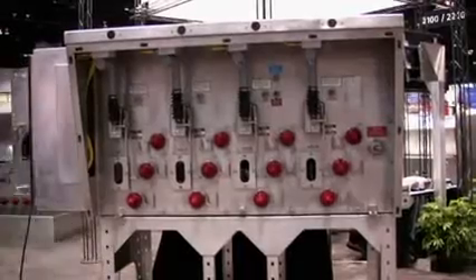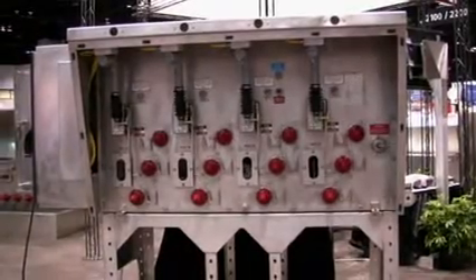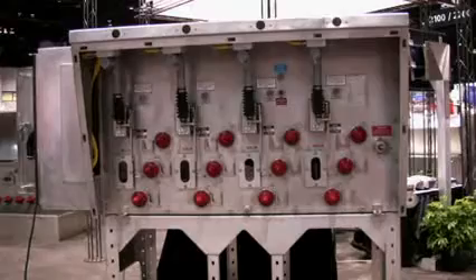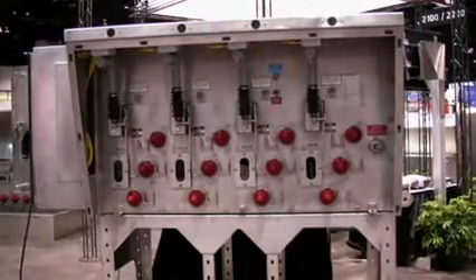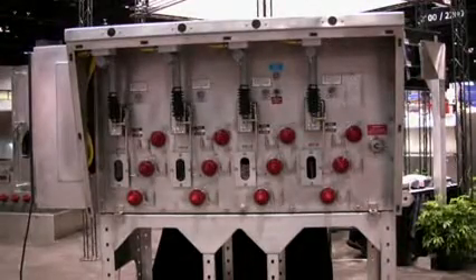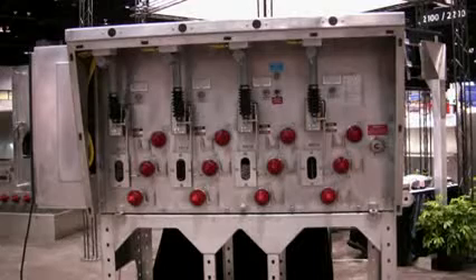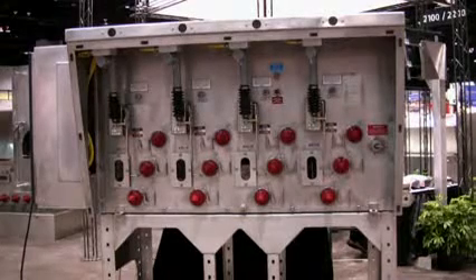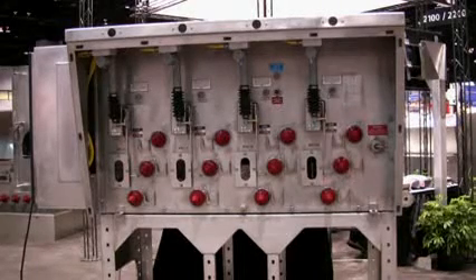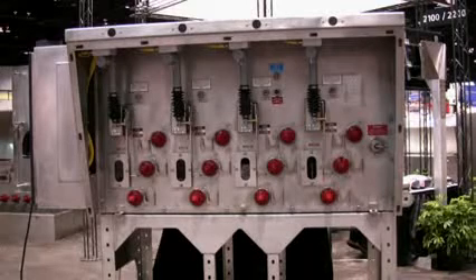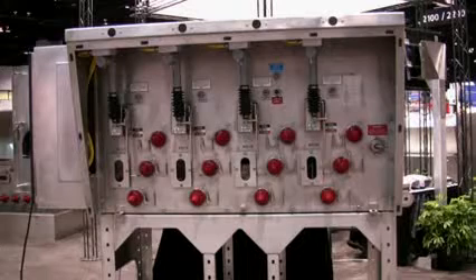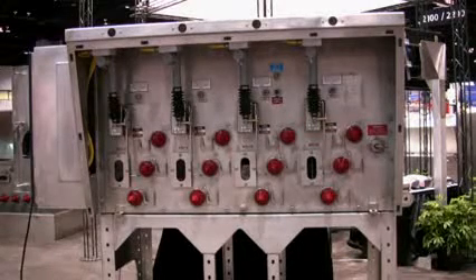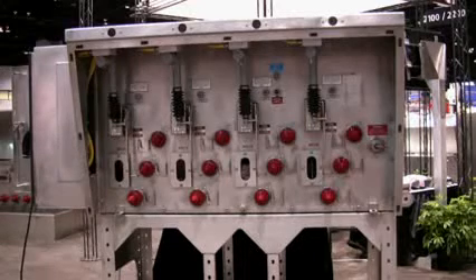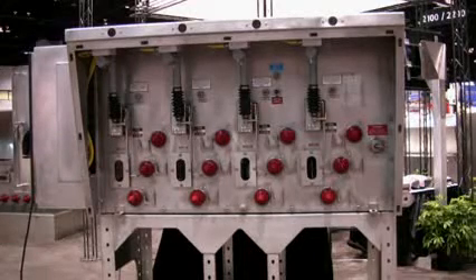This particular unit is a 4-way vault mount unit, fully automated. It has 4 ways with vacuum fault interrupters, with visible disconnects in series, with motor operators, so everything can be operated remotely. It has current transformers on all ways, and it has voltage pickups. So all switching, interruption, and sectionalizing can be done remotely and or locally.